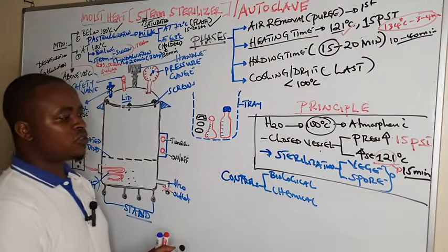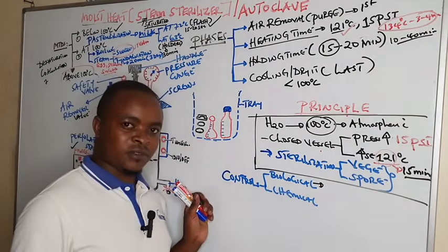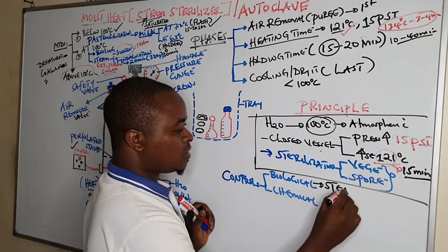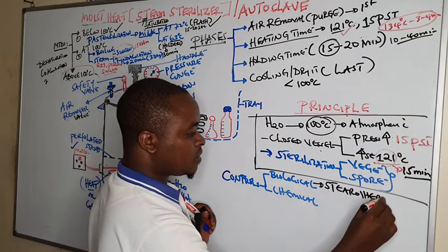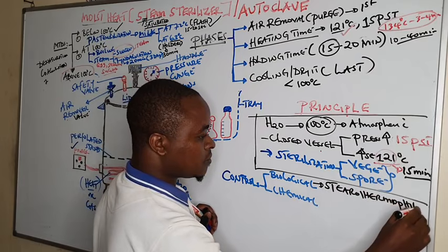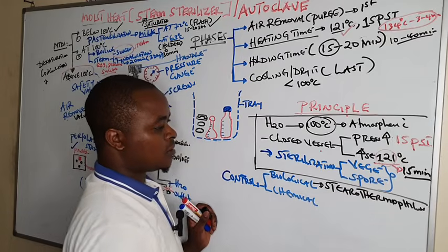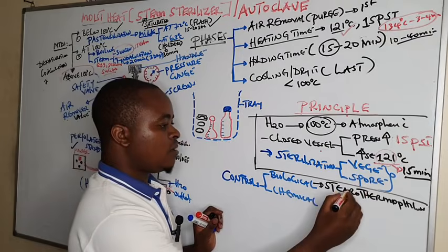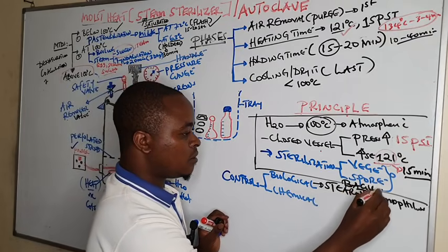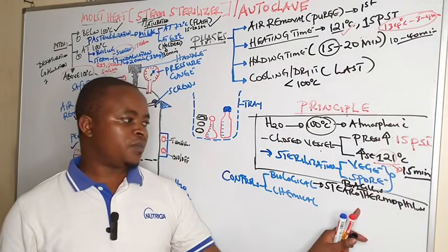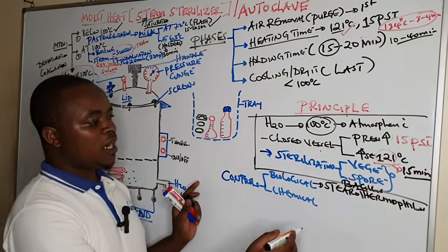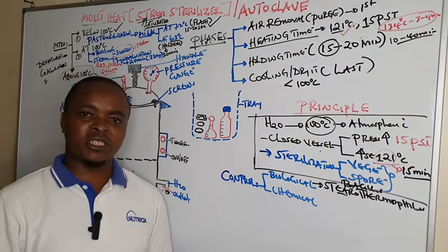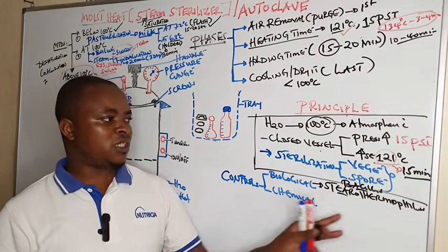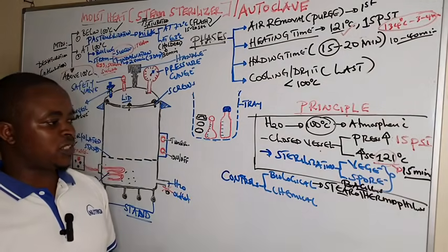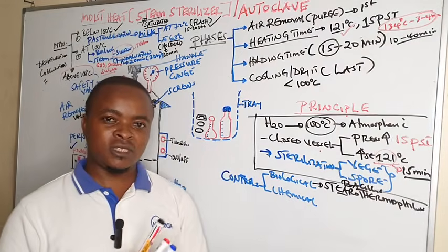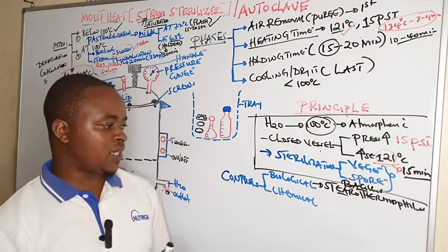And under biological control, we have a bacteria which is a thermophile, that is Bacillus stearothermophilus. This is a thermophile which can be used as a control because, for it being a hyperthermophile organism, it can survive at high temperatures. So we normally use it as a control, that when we find it is already killed, it tells us that we achieved maximum sterilization.